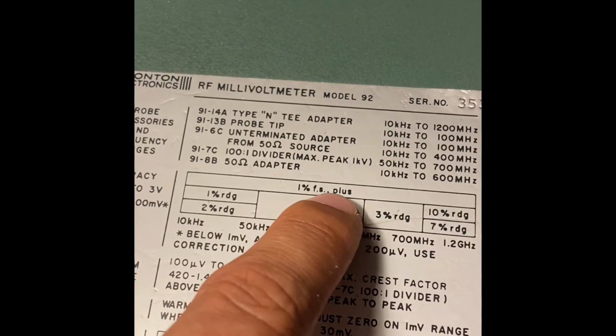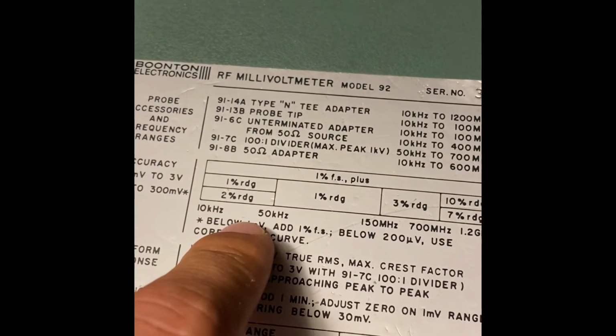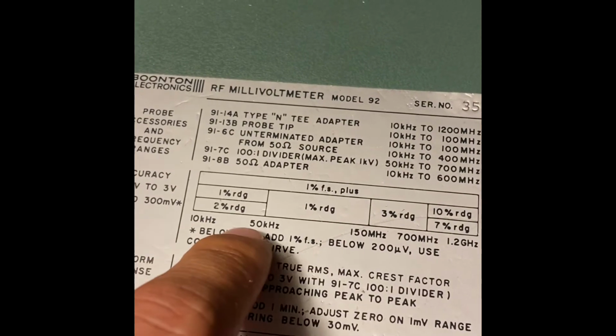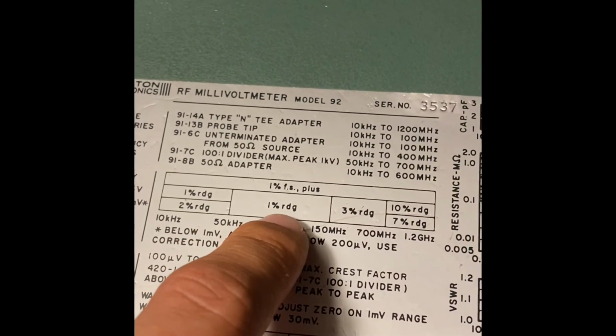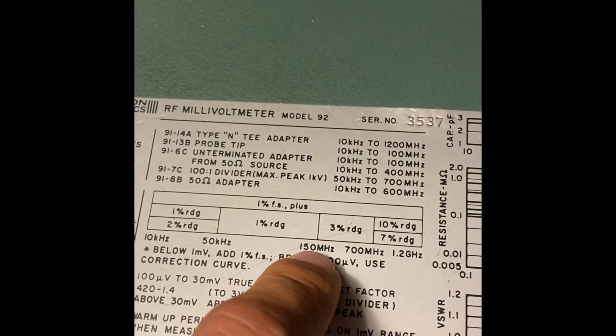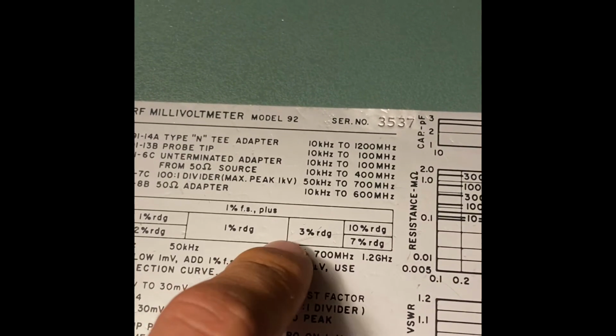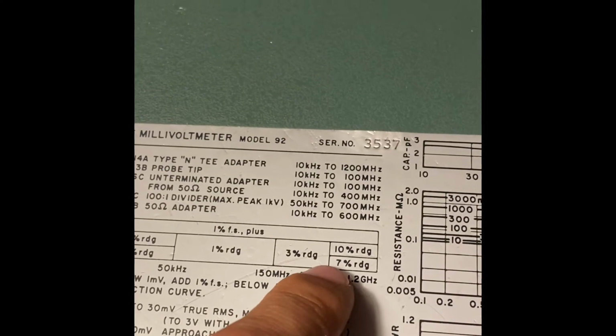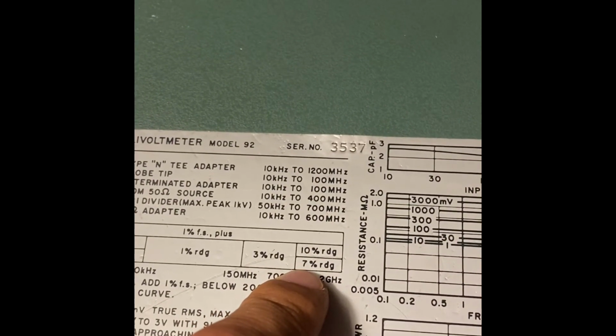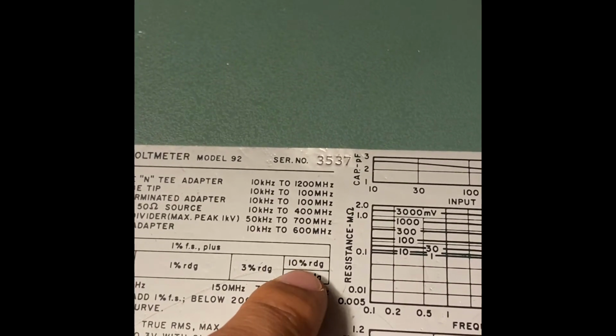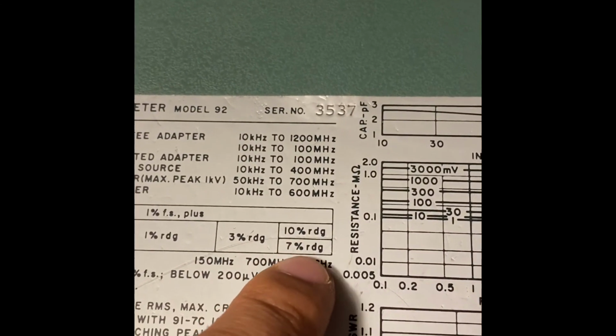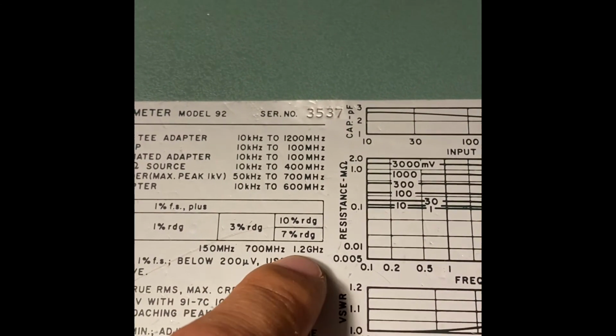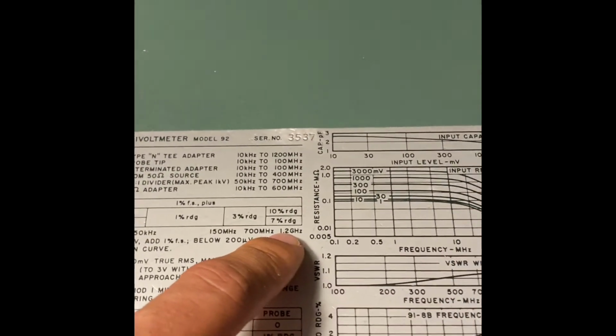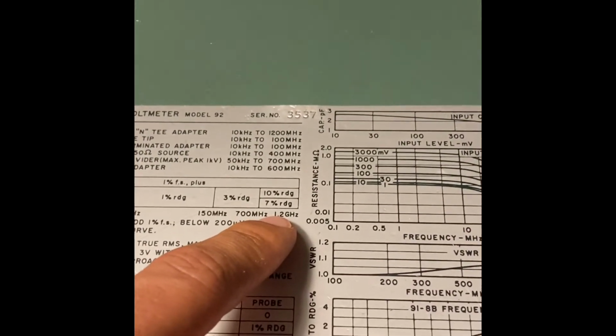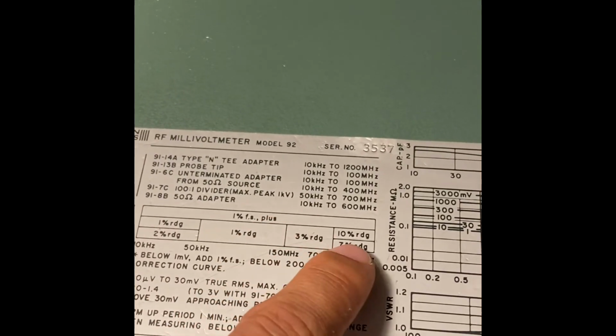So we've got 1% full scale plus 1% reading in the lower part up to 50 kilohertz. Then it's 1% reading also up to 150 meg. And then it becomes 3% reading up to 700 meg. And then you lose quite a bit in accuracy, because here we have 10% of the reading up to 1.2 gig. So in effect, if you go in the 1 gig frequency, you've got this quite big error.